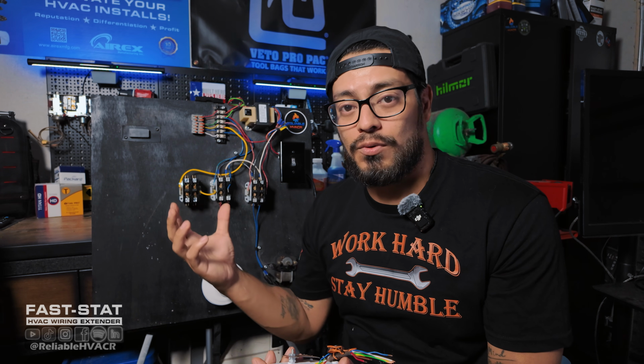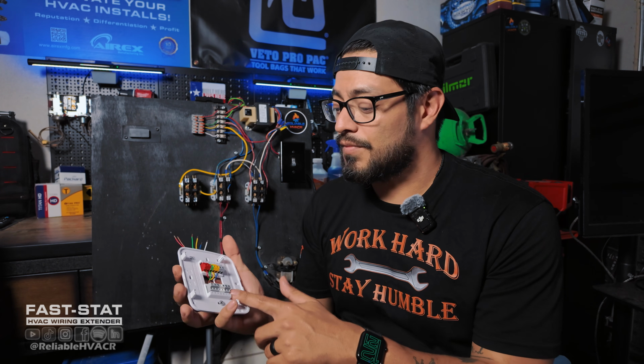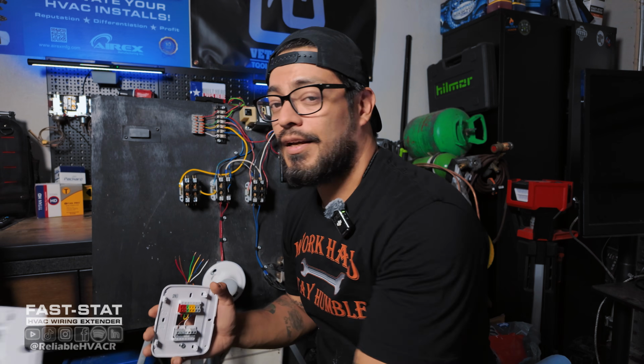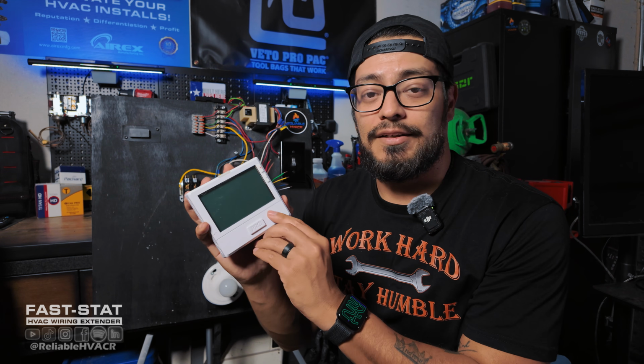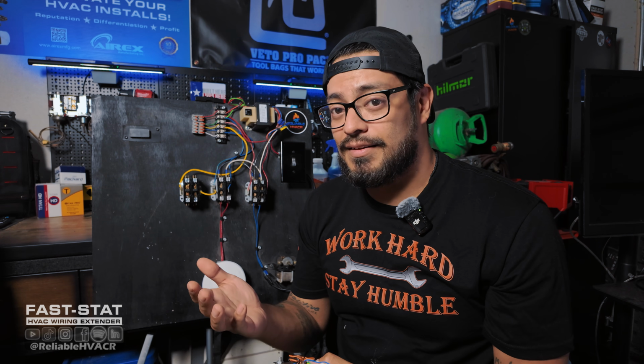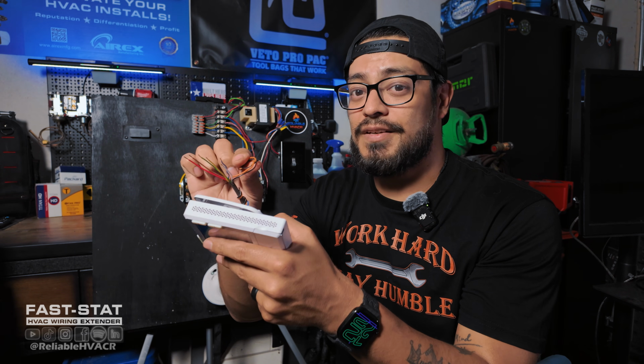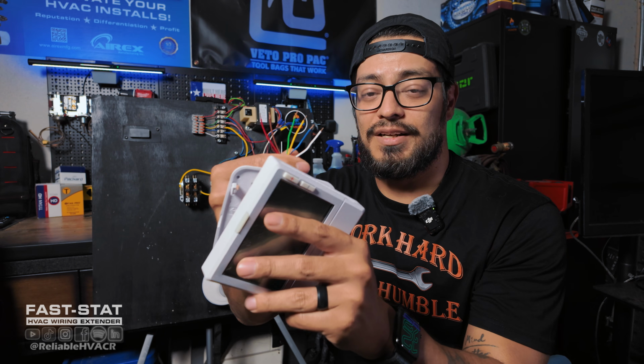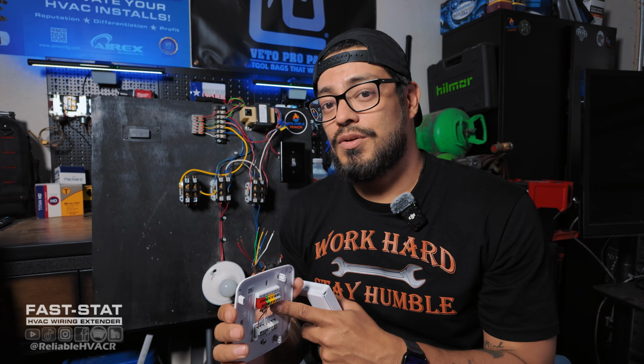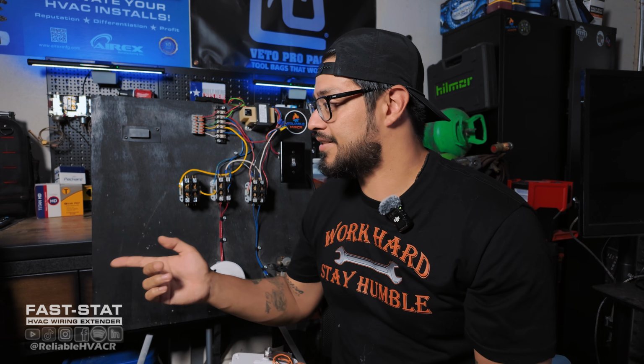Usually there's a common on a terminal board, a control board that you can hook it up to. Maybe nobody hooked it up. That way, if the battery ever fails on it, it can still run. That won't be a nuisance call. Now, again, let's say you don't have any extra wire, you're stuck with just whatever is being used. Technically, you could steal a wire, but then you're going to lose your heating or whatever, second stage, whatever it is. Or you could get a Fast-Stat common maker.